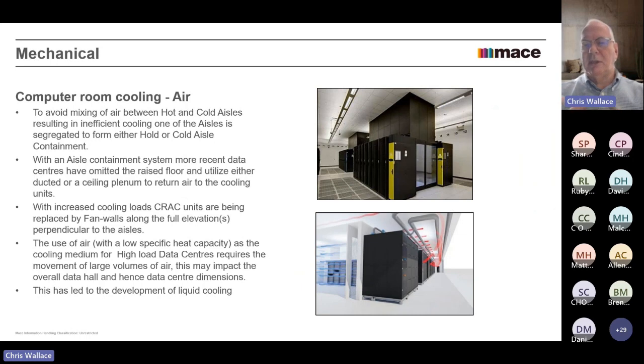More and more as time goes on, that top picture is a sort of halfway house, because you've got a floor void, a floor plenum, and you've got a ceiling plenum. As time's gone on, what people are doing is getting rid of more and more of the CRAC units, and they're replacing them with fan walls. So what's a fan wall? Basically, it's just a whole series of fans blowing through coils at one end, on one elevation, the elevation that's perpendicular to the aisle, and they blow cold air down the cold aisles, basically.